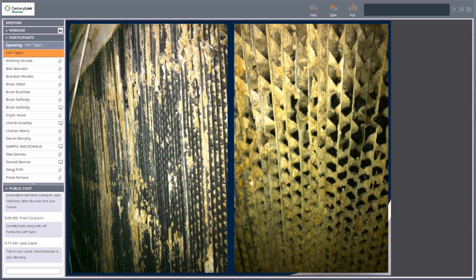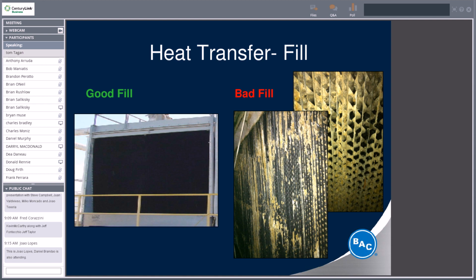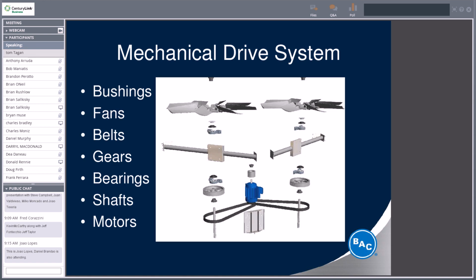The drawing on the left, as you look at it, is actually not bad compared to the drawing on the right. So if you look at good fill versus bad fill, obviously it's pretty obvious that on the left you've got a pretty clean tower operating at peak efficiency. On the right, you've got a pretty scaled up piece of equipment. Eventually, it will be scaled up and fouled up enough where you may need to pull it down and try to clean it, or eventually replace it in place. The mechanical drive system we talked about on this specific induced draft prop fan tower, you've got your bushings, fans, belts, gears, bearings, shafts, and motors.